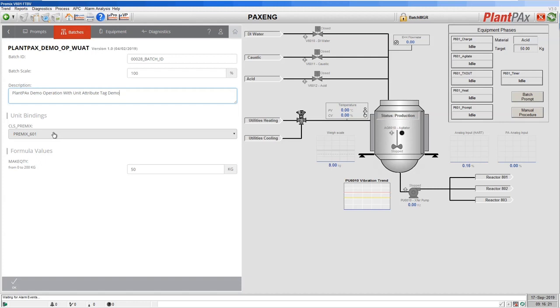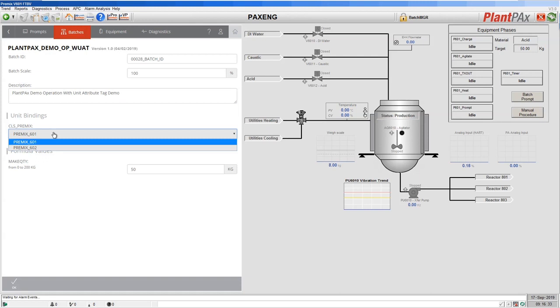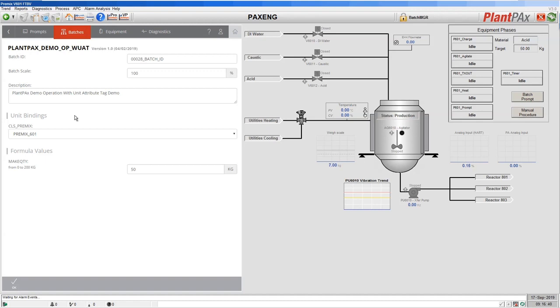This means that if your plant had multiple pieces of equipment that can do the same thing — say three mixers that can each make the same product — you can write a recipe once and that recipe can run on any of those mixers. Here I've got a recipe that has to run on a pre-mixer and I can choose any of my pre-mixers in the plant. I'm going to choose the first one. Finally, I have some things which I specified in the recipe have to be asked on recipe creation, so for this recipe I have to specify how much to make — let's say 100 kilograms — and then accept our options.